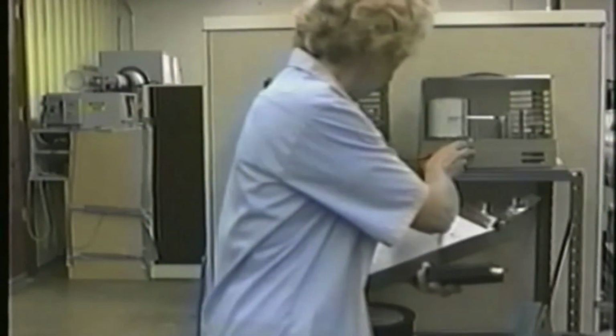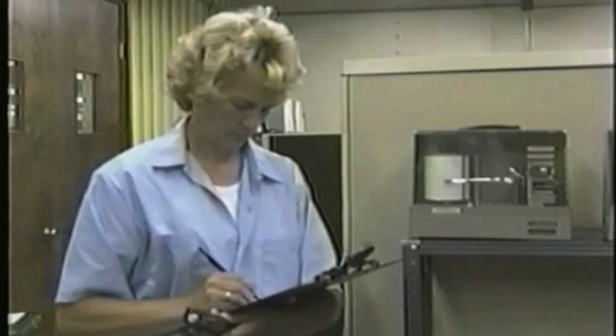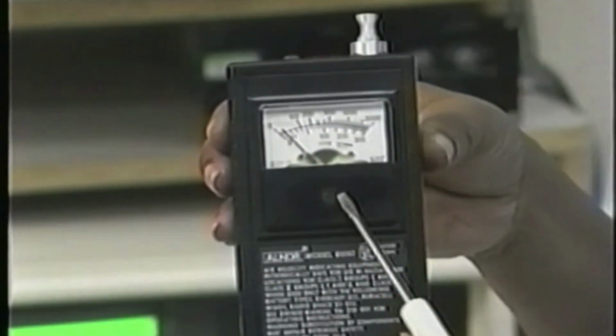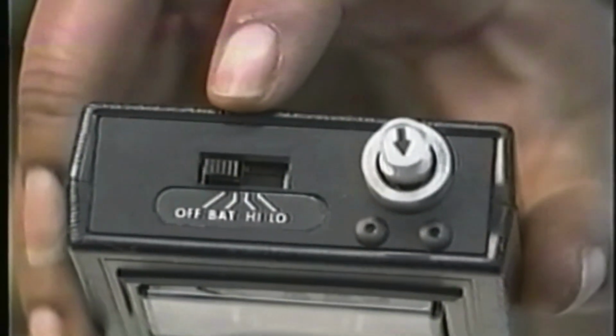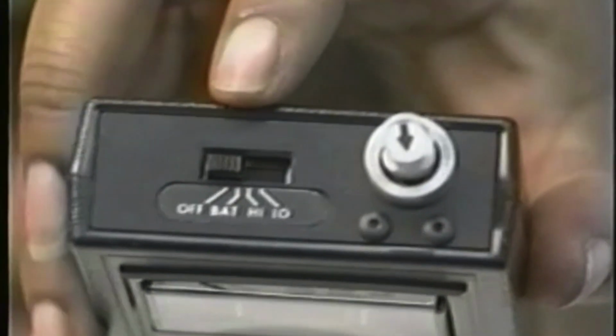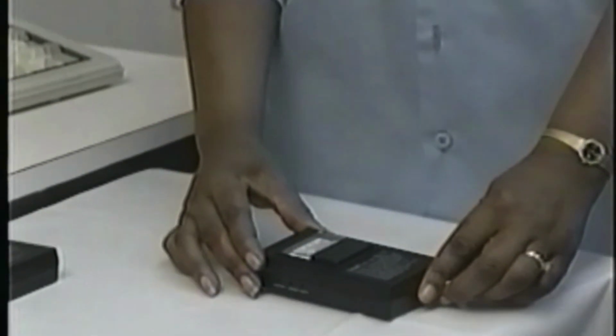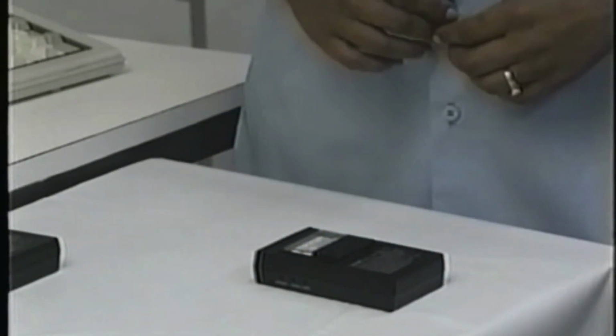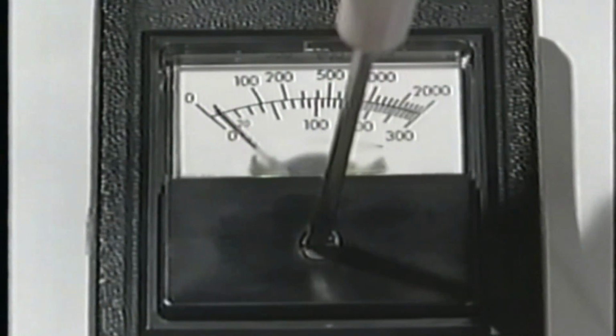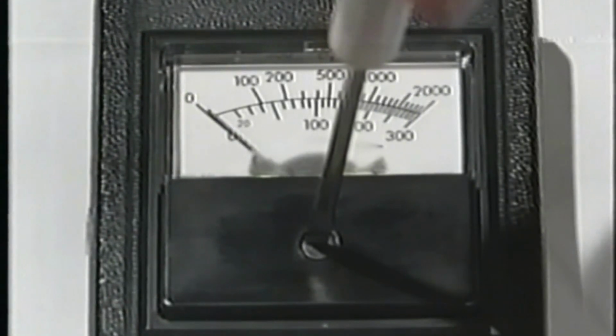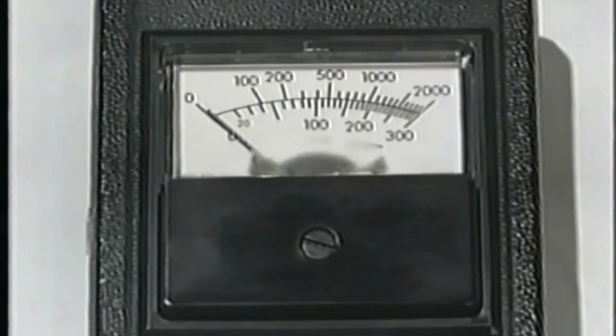Keep in mind that a change in any one adjustment requires calibration of the zero adjustment, high range span adjustment, and low range span adjustment. The 9850 is calibrated by first setting the zero reading mechanically and electrically, and then setting the low range span and high range span. The mechanical zero adjustment consists of turning the instrument to the off position, laying the instrument on a flat surface, and viewing it directly from above. Using a screwdriver, the screw in front of the unit should be turned so that the meter needle is lined up with the zero division.